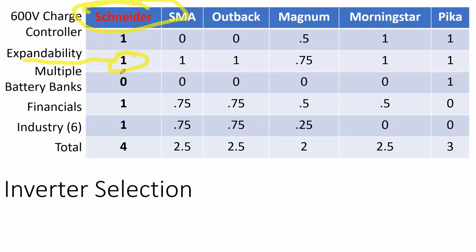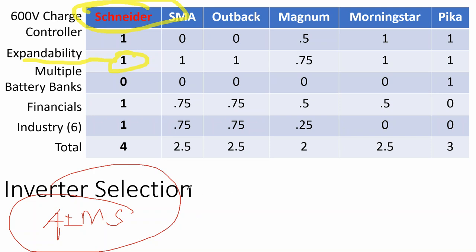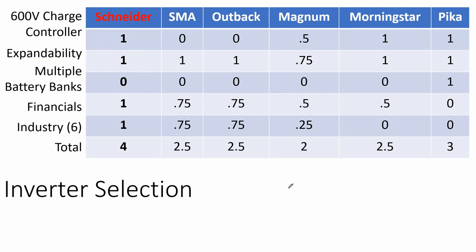But sometimes the inverters that are designed to be purely off-grid, the company that leaps to mind is one called AIMS, which is not on this list, are not. Their off-grid inverter is not listed for grid connection, and it's substantially cheaper than any of these companies. It's a pure sine wave inverter with surge ratings and a lot of good features built into the cabinet. But it's not stackable. It's not expandable, which means their maximum inverter size is 12 kilowatts. So if you're doing a higher end home, maybe that home's power demand, if they have a swimming pool, or if they do a tankless water heater, they don't make a product that would serve that higher demand. So not all battery inverters are expandable.